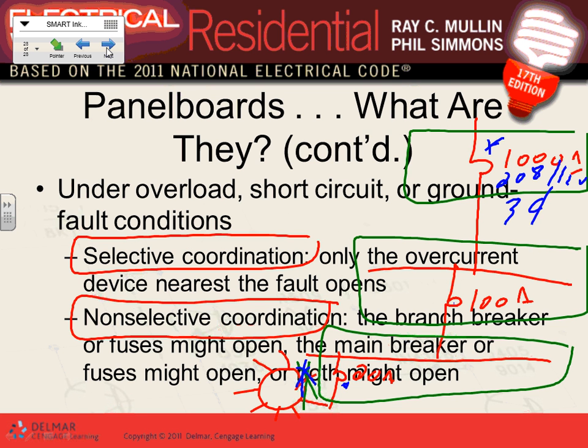And then we'll start talking about how it did happen in hospitals, it happens in a lot of places, especially with the ground fault. We'll talk about ground fault later, guys. In a system of 1,000 amp or higher, you're required to have ground fault protection because the circuit breaker becomes so big that it cannot see a ground fault. It sits there and burns without being seen. So they add another protection called ground fault protection that looks just at the ground fault. It's only required on 480/277 systems of 1,000 amp or higher. So if you haven't done 1,000 amp or higher, you've never heard of it.